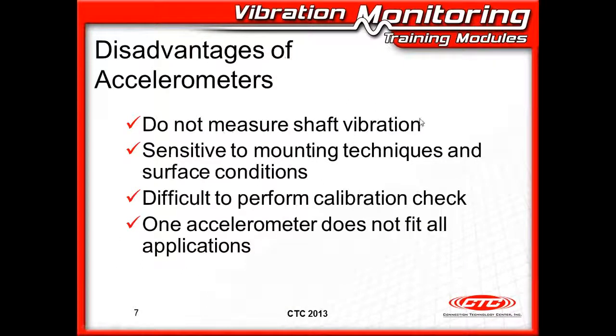Disadvantages of accelerometers: they don't measure the shaft vibration, as we've just seen in that fluid film bearing. They're very sensitive to mounting techniques and surface conditions. We need to have a really good mount so that we transmit that vibration into the sensor. It's difficult to perform a calibration check. You need a nice shaker and good mounting methods and good accuracy on how you measure that output. And of course, one accelerometer doesn't fit every application. So you should have a series of different accelerometers for different applications.